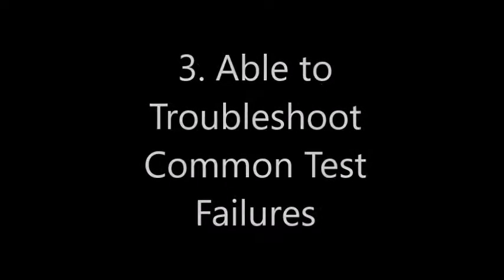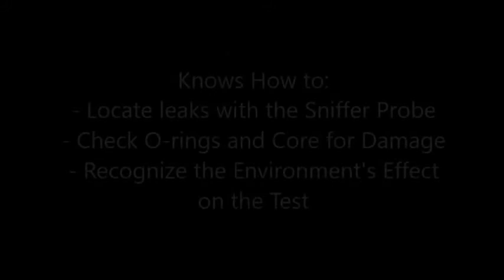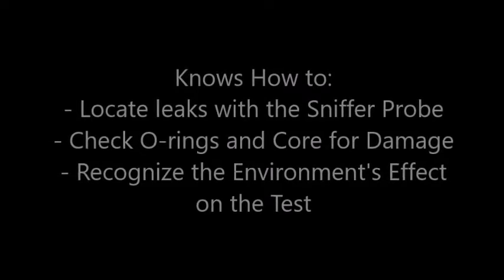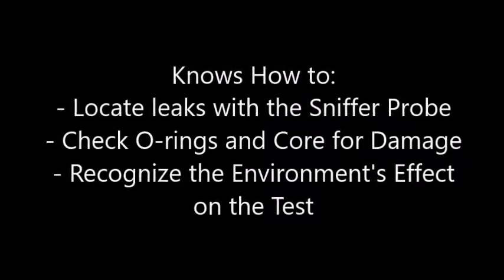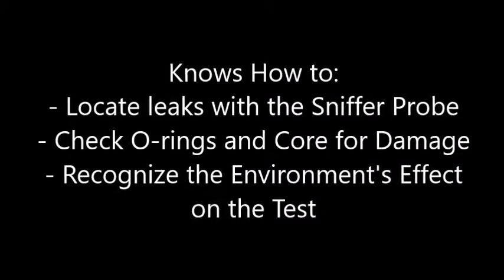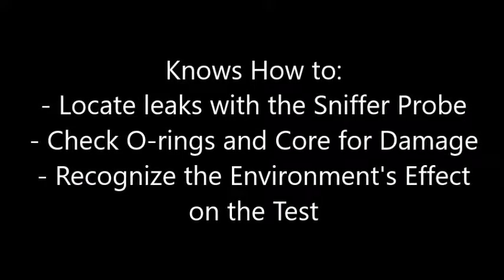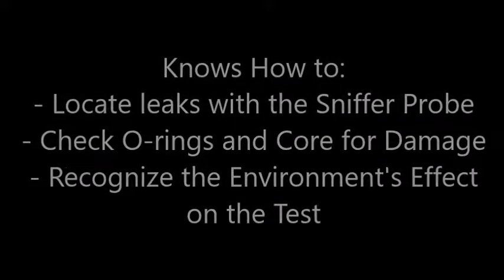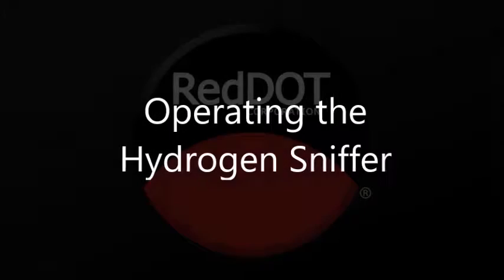And number 3. The operator is able to troubleshoot common faults that happen during testing. This means the operator knows how to locate leaks with the sniffer probe, knows to check for damage to the O-rings or core, and recognizes the effect the environment can have on the leak test. That's all you need to know about operating the hydrogen sniffer.